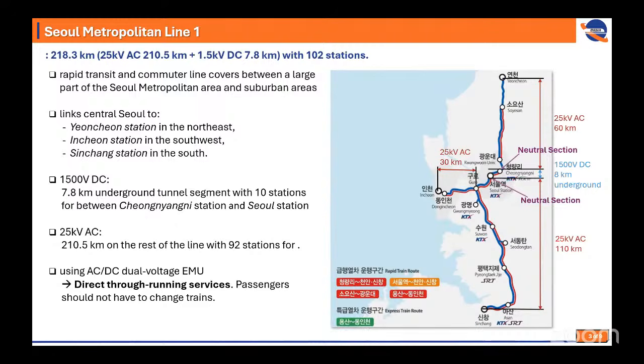As you might know, a train cannot be directly connected to both AC and DC power, because it would create a serious electrical problem. Therefore, a special section called the neutral section is installed between the two power systems. In the case of Line number 1, when the train approaches the transition area near Seoul Station or Cheongnyangni Station, the traction power is temporarily disconnected. Then the train coasts through a short unpowered section, the neutral section, which has a length of 66 meters. This 66 meters is required by Korean regulation.